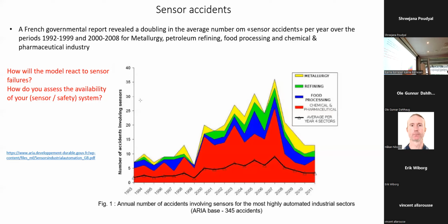Anyway. Just a comment on that, because a lot of your models here are linear models. You can detect temperature rising in the bearings, vibrations in the bearings, which will have maybe a linear tendency, but these material failures are very hard to detect. The material breaks. So the complexity in this model, there will be a lot of parts in this complex model for the whole system that will not have any tendency, will have sudden failures. And these are really difficult to model and to detect problems.